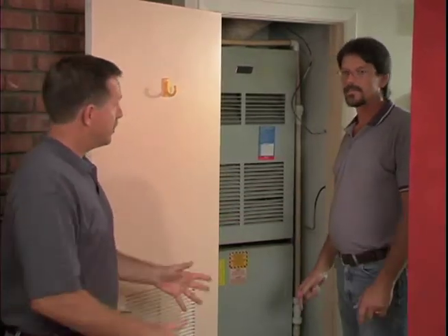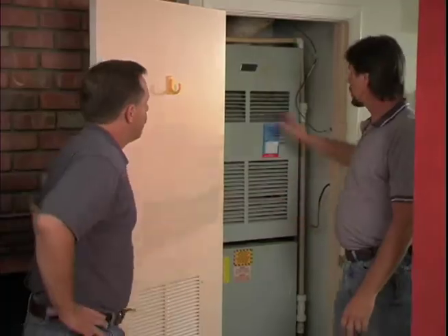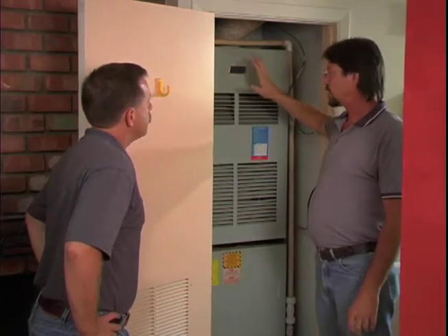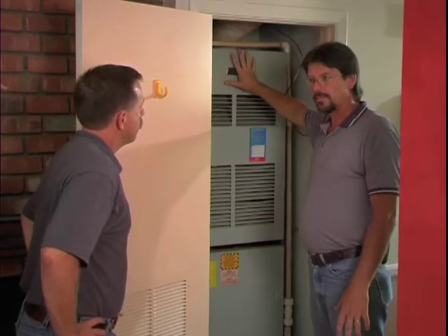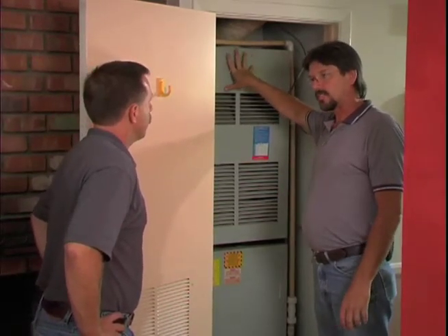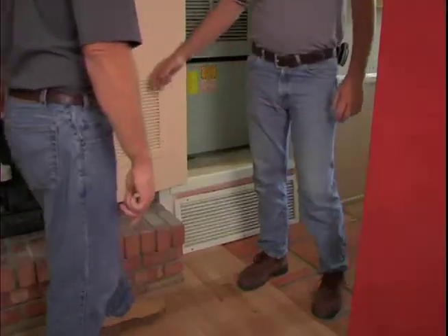So you're saying this vent makes a connection from the inside of the home to the closet, into the attic, then ultimately outside? Exactly. How do we fix that? Well, what we want to do is get rid of this combustion air here. And there's a couple alternatives. We can either take this piece of equipment and move it outside, or get a sealed combustion furnace so we can eliminate these vents, or we can just move to a whole other heating source. Okay, great. Did you find anything else here? Yes, we did. We could shut this door. Sure.